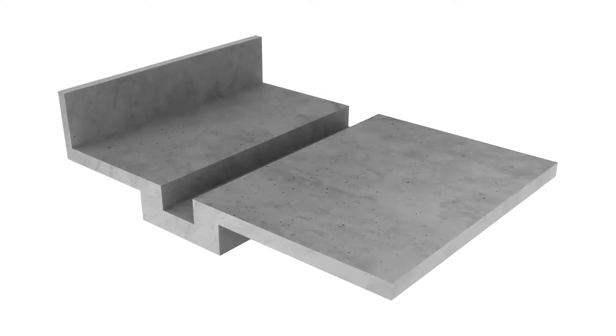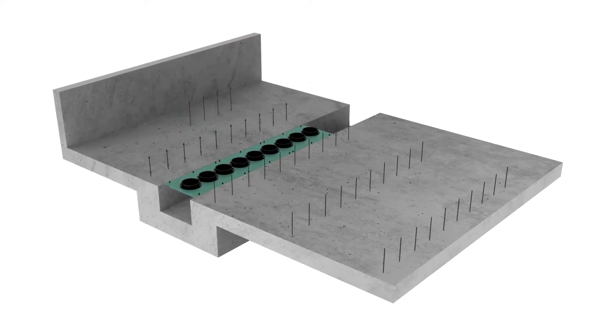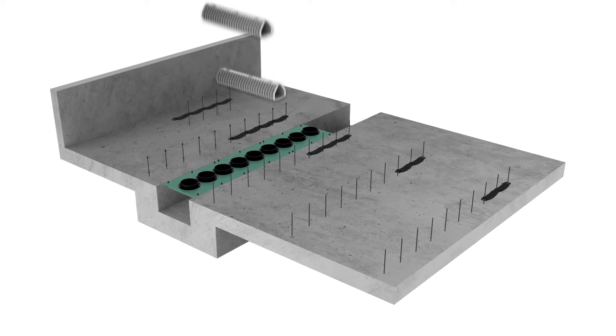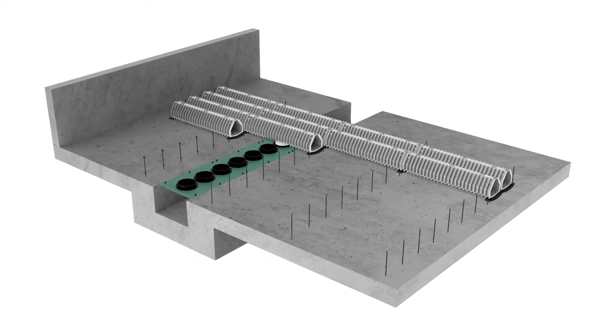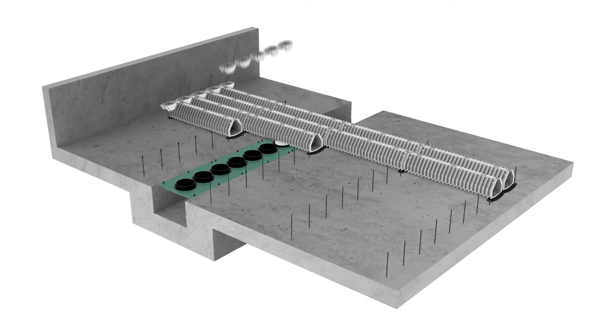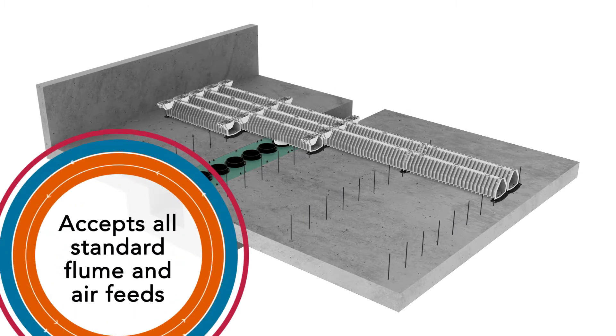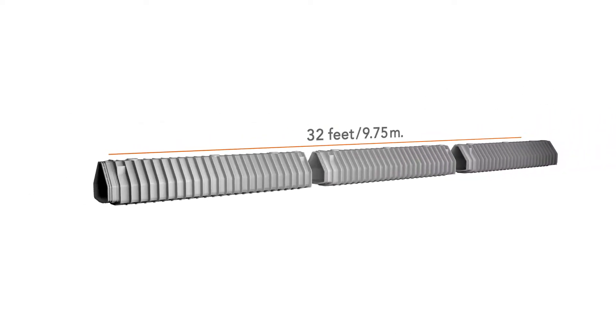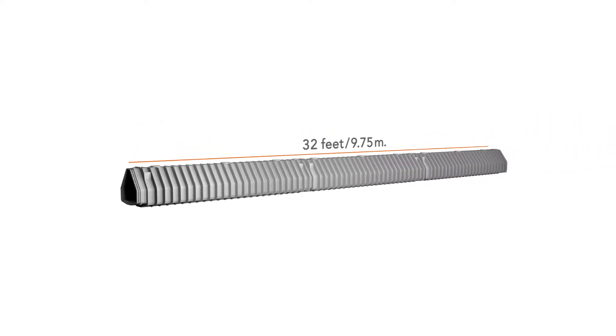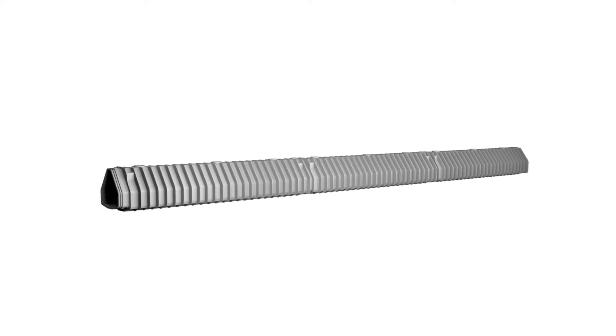The all-new bolt-down underdrain design of the Type 360 simplifies installation and serviceability. The modular pieces fit together quickly, reducing installation time and costs. Custom hold-down brackets make it easy to anchor the filters, and it is adaptable for all standard flume and air feeds. With lateral lengths of up to 32 feet or 9.75 meters, the Leopold Type 360 underdrain system is ideal for both new installations as well as retrofits of existing filters.